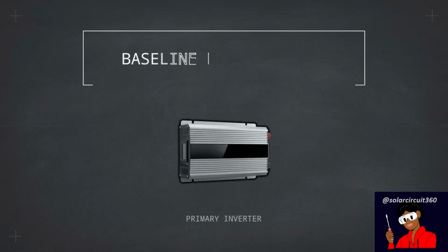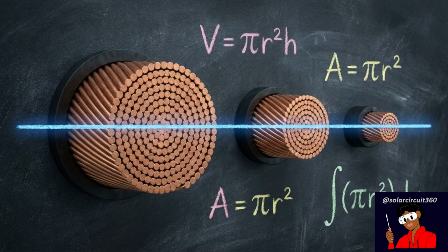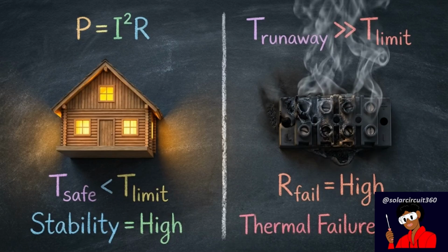We will use a strict baseline testing parameter, a heavy-duty 3,000-watt off-grid inverter load. The central question is what happens to the physical wiring required to sustain this exact 3,000-watt load as we manipulate the system voltage. The mathematics behind that single variable will dictate whether a solar system safely powers a home or physically melts its own terminations.